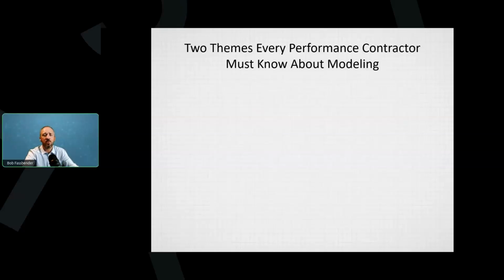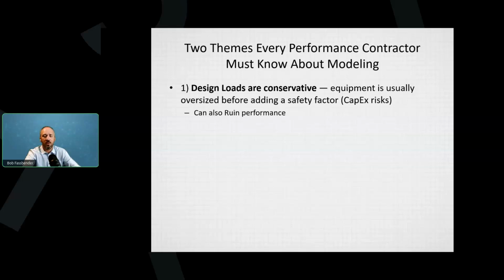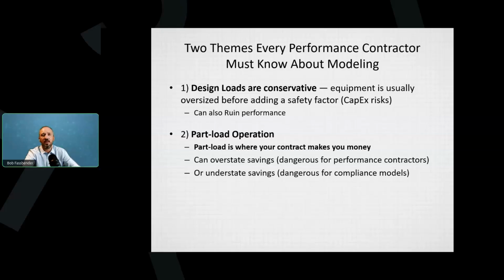So there are 2 themes I want to focus on. One, and I think anyone who's been in the field knows this, design loads are conservative. Equipment is usually oversized. And in the model, that happens before you add a safety factor. And from seeing thousands of models, I can tell you that pretty much everyone adds a safety factor. That's a risk on capital expenditure, but it's also a risk on performance. The next item that you really have to know is that part load is where your contract makes money. That's where the building spends 99 point some percent of its time.